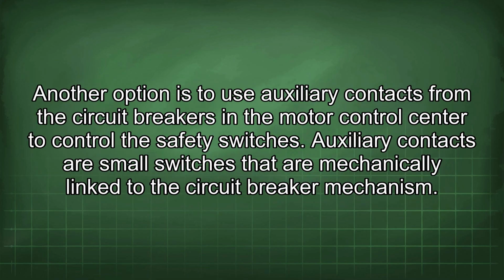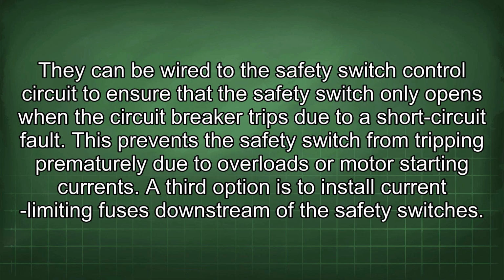Another option is to use auxiliary contacts from the circuit breakers in the motor control center to control the safety switches. Auxiliary contacts are small switches that are mechanically linked to the circuit breaker mechanism. They can be wired to the safety switch control circuit to ensure that the safety switch only opens when the circuit breaker trips due to a short circuit fault. This prevents the safety switch from tripping prematurely due to overloads or motor starting currents.